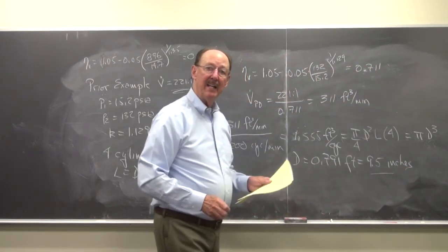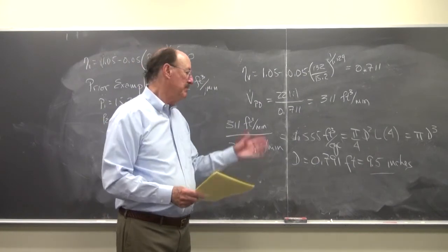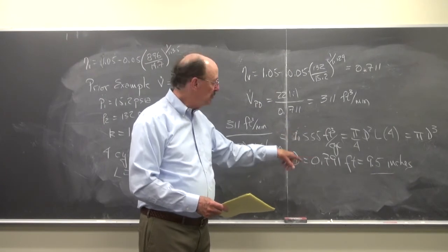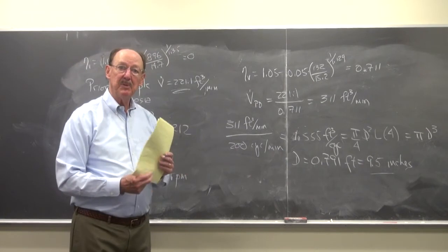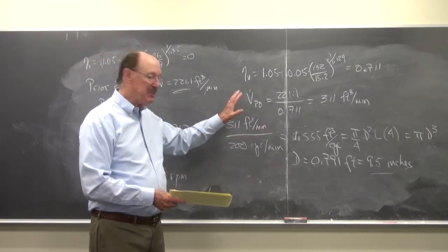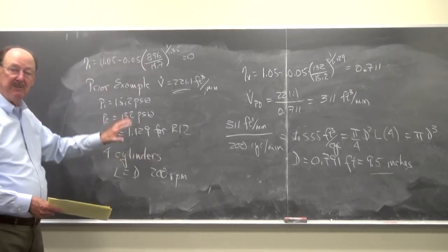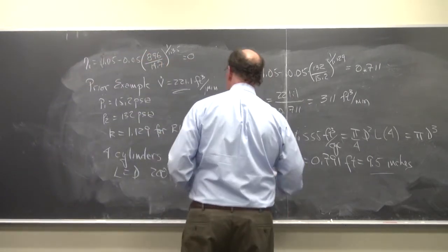And obviously if I had a faster RPM, then it would change, and I just picked 200 for this example, so we would have 4 pistons, and this would give the bore and stroke of that amount. And now let's look at some compressor performance factors. So this is how I can size the compressor knowing information like my volumetric efficiency, and it gives me the ability to size how big the compressor should be.